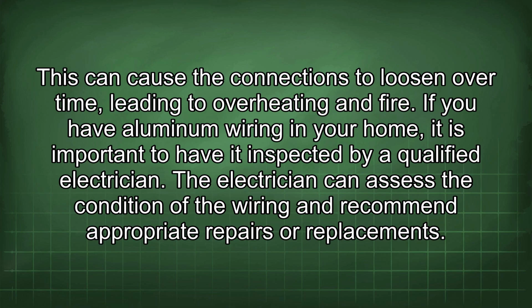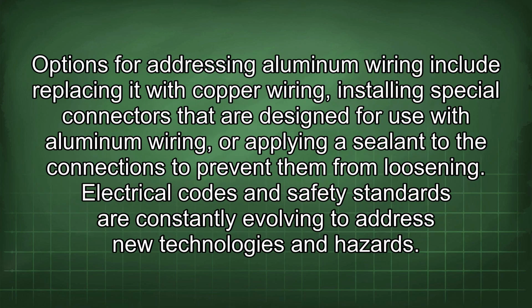If you have aluminum wiring in your home, it is important to have it inspected by a qualified electrician. The electrician can assess the condition of the wiring and recommend appropriate repairs or replacements. Options for addressing aluminum wiring include replacing it with copper wiring, installing special connectors that are designed for use with aluminum wiring, or applying a sealant to the connections to prevent them from loosening.